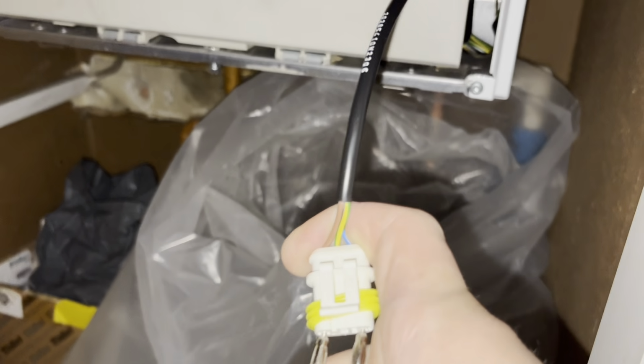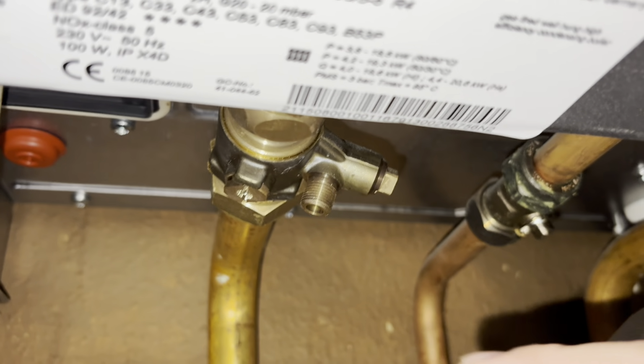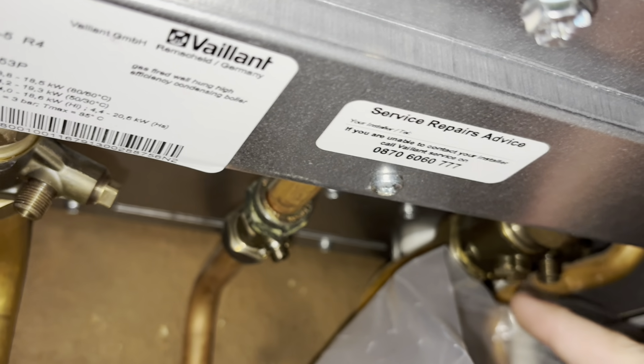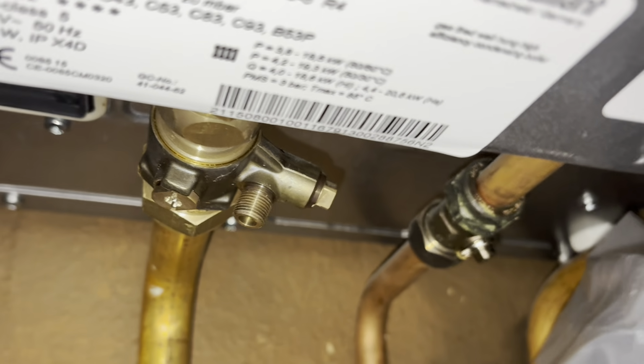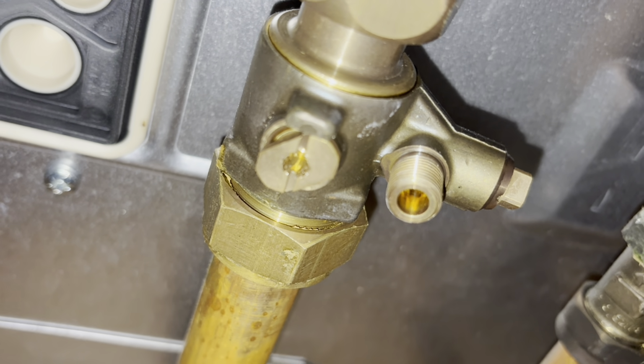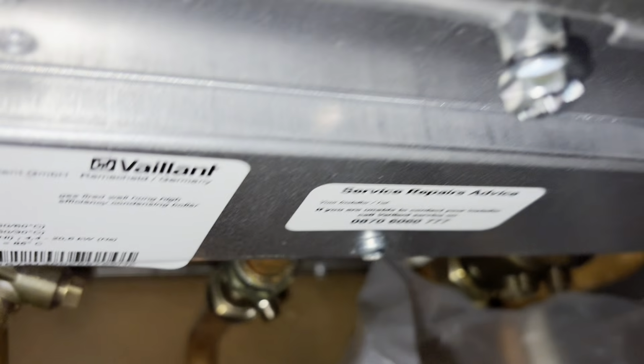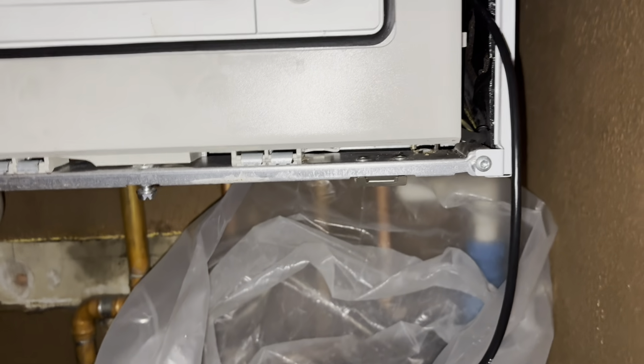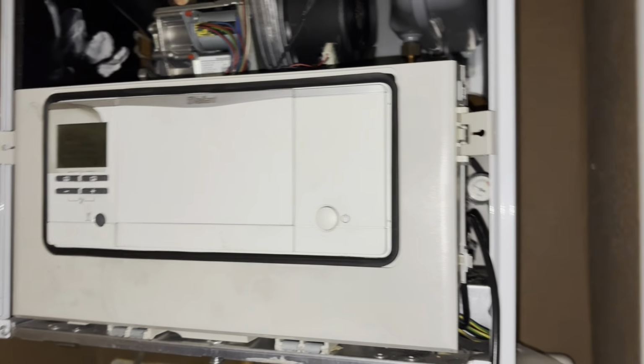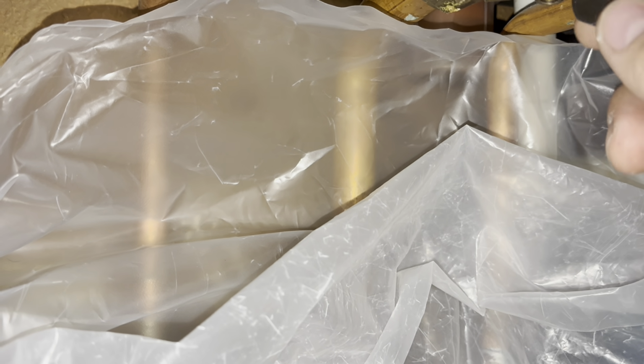Now, pump change. So ideally, before you start, if your boiler is at the highest point in the house, you would want to use your Allen keys and turn off the flow and return. But unfortunately, it looks like someone's bored out this hole and I cannot shut it off, so we will just be draining it down. So, key, small bag underneath, open up the drain.